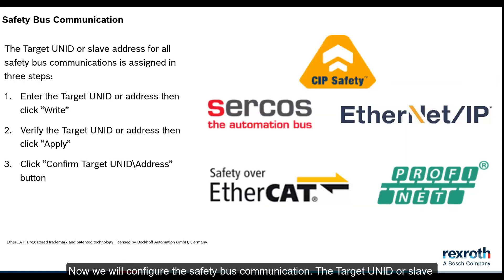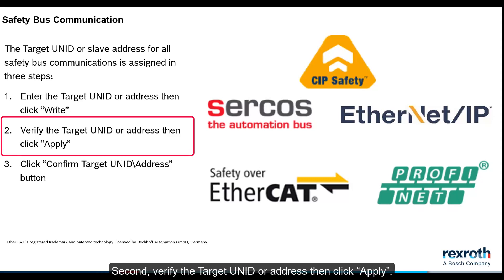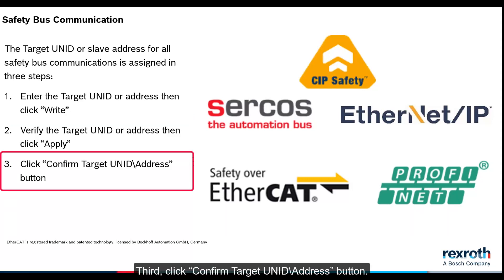Now we will configure the safety bus communication. The target UNID or slave address for all safety bus communications is assigned in three steps. First, enter the target UNID or address, then click write. Second, verify the target UNID or address, then click apply. Third, click confirm target UNID address button.